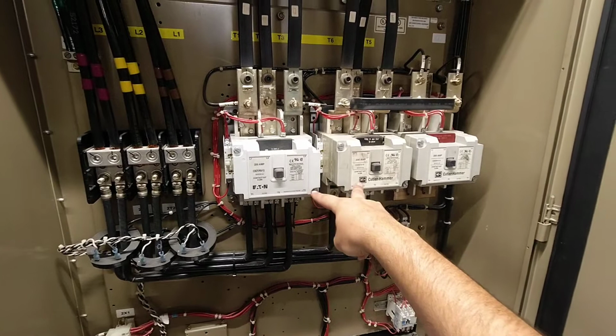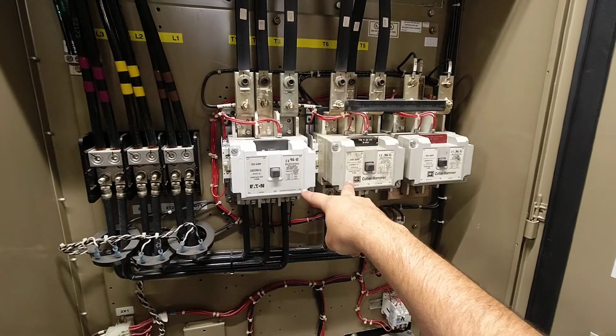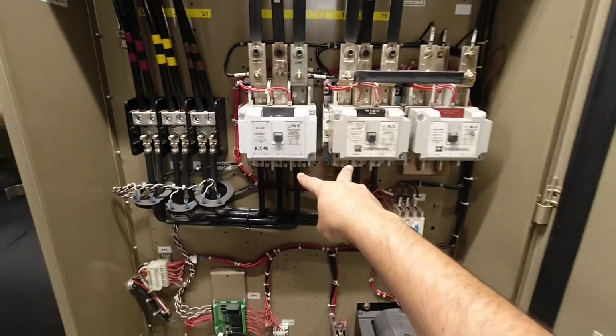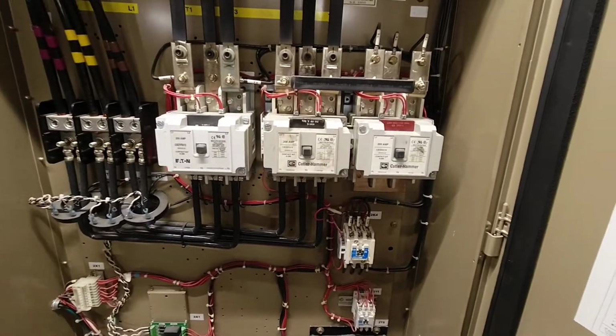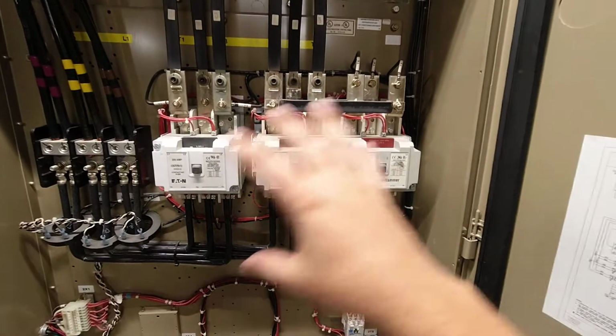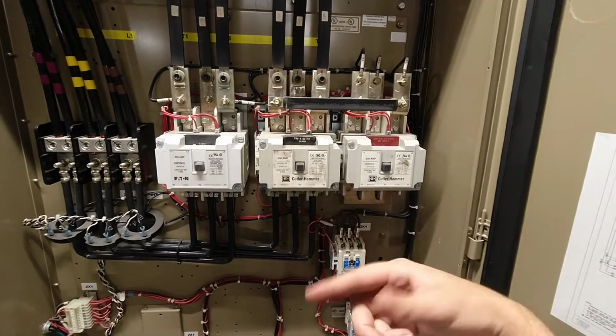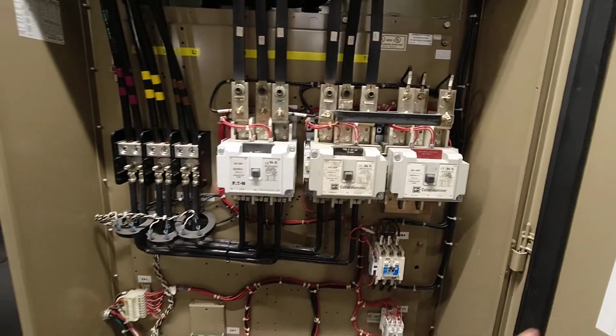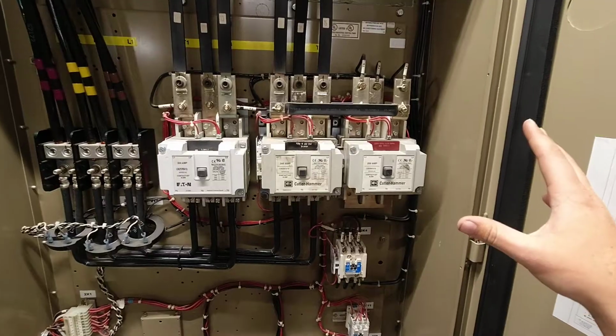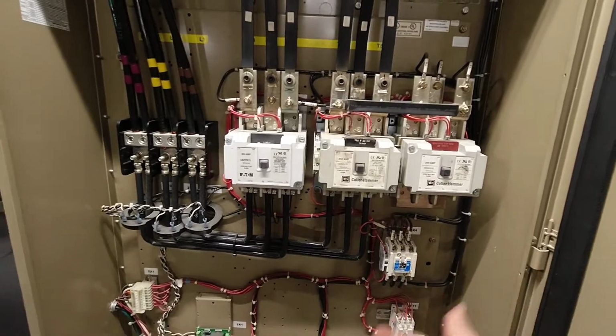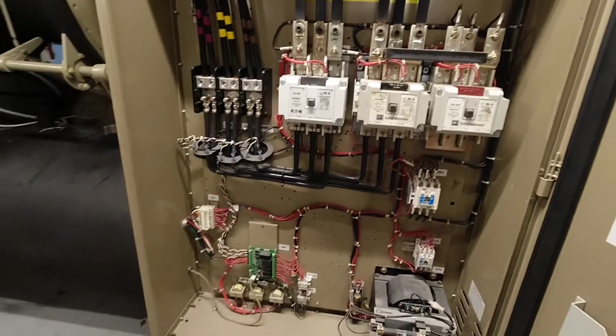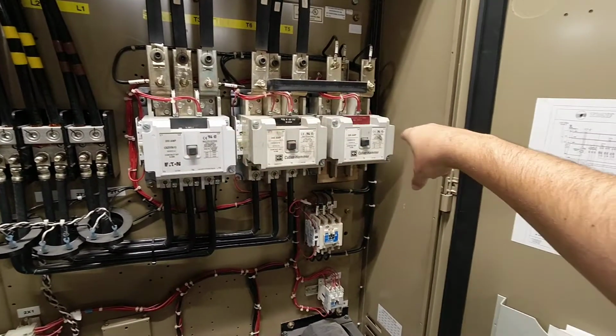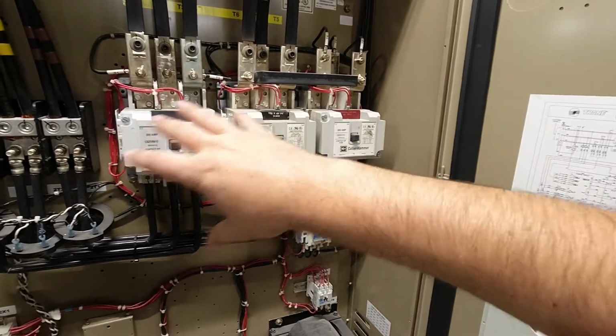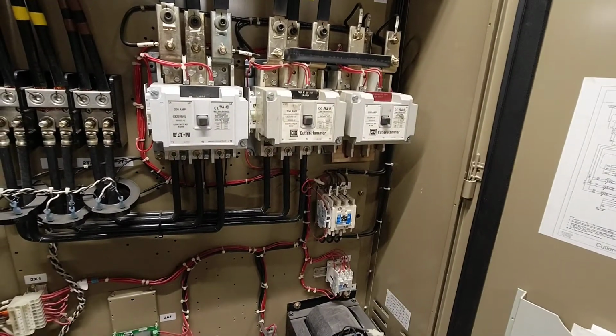At the end of it, once it's started, these two here will be the two that are constantly on throughout operation. The point of that whole start sequence is to get some pre-rotation on the chiller motor so that it will make less inrush current at startup. You do definitely need to make sure you maintain the contacts, the coils, everything on those very, very well.